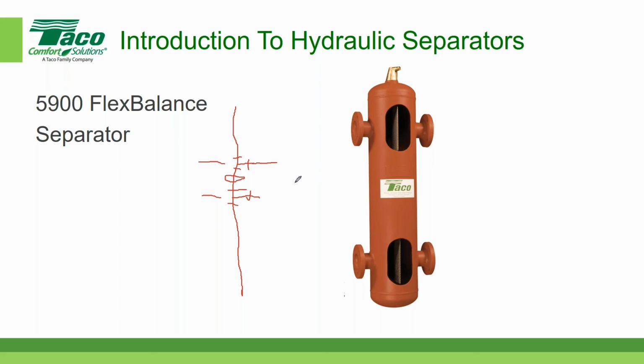What most people do is they'll dramatically oversize this pipe. Let's assume that this main happens to be 12 inches. I'm making up a number here. And the bridge itself, they might size that at 16 inches and then make the T's far enough away so that there is no unanticipated mixing and the pressure drop is negligible.